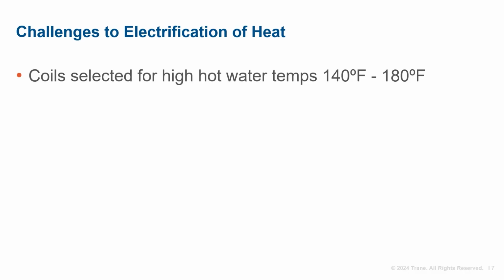Sure, Jeanne. With the industry and an increasing number of building owners looking to lower their carbon footprint, designers are being asked to electrify building heating systems. We've covered design trends on electrifying new buildings in previous E&Ls, but electrifying existing buildings presents several unique challenges that need to be addressed. The first and most common issue is that existing coils are selected for elevated hot water temperatures, often 180 degrees Fahrenheit.